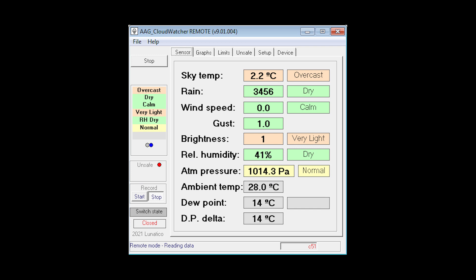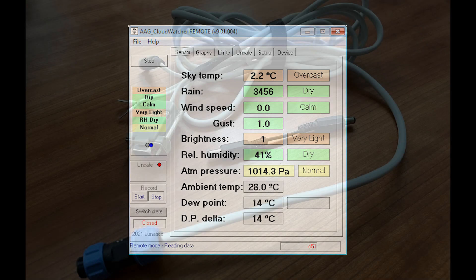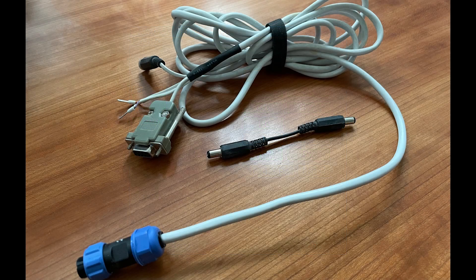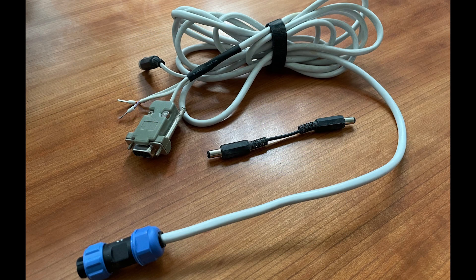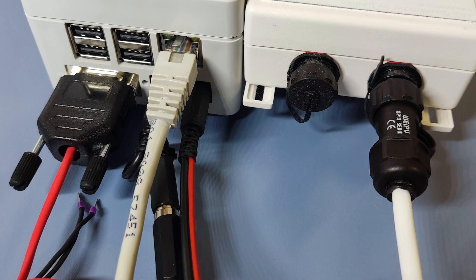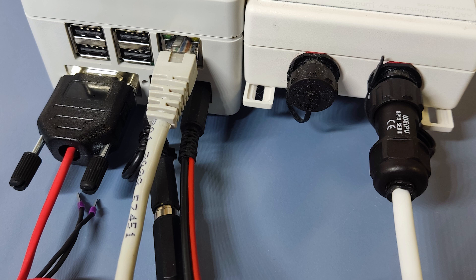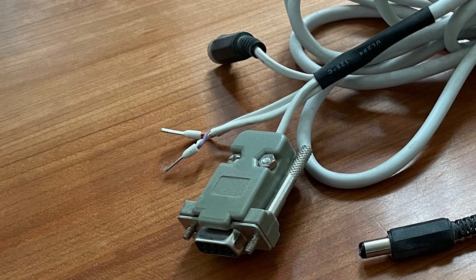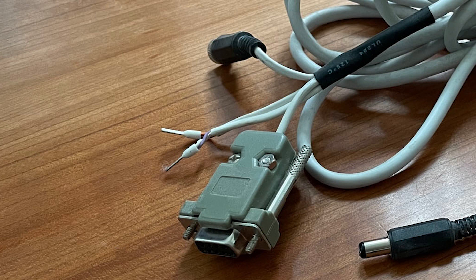We've seen how the CloudWatcher interacts with the Solo, but how else can it be connected to your observatory equipment? Well, the answer is in two ways. When you order your CloudWatcher, you also choose a multi-function cable with a range of lengths up to 10 meters. Two wires in the cable provide a general purpose means of communicating if the weather is safe or unsafe.